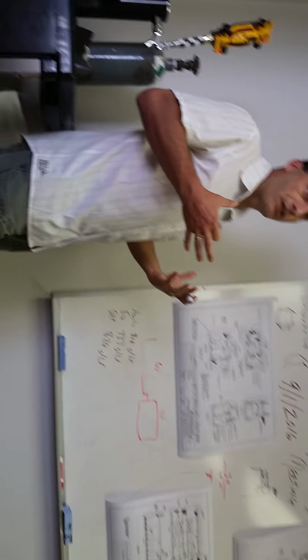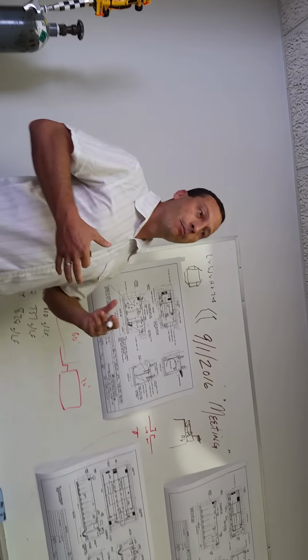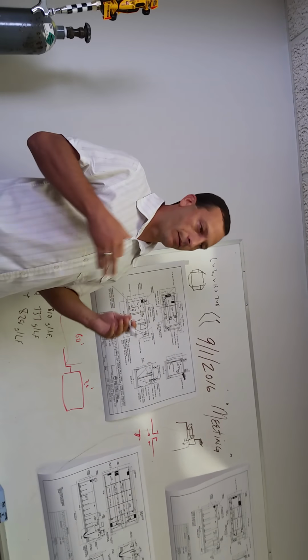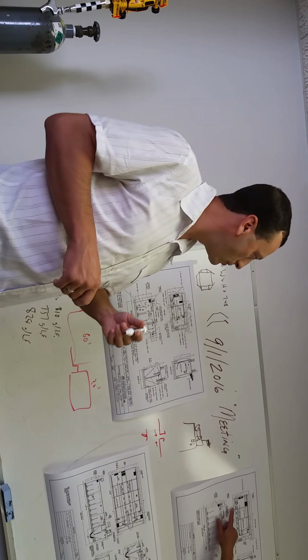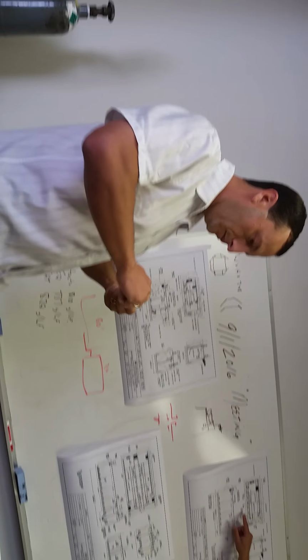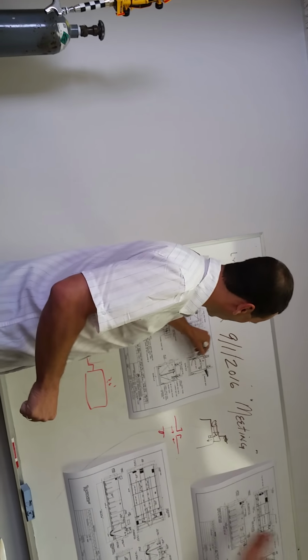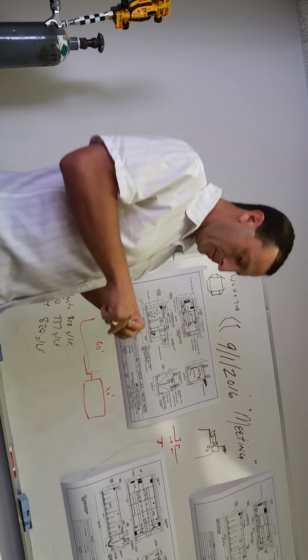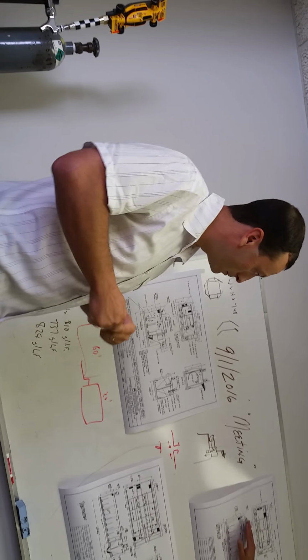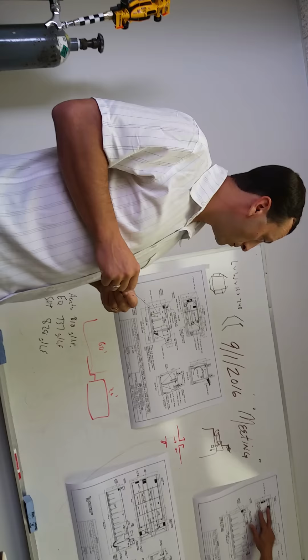So that's the other reason for the shape: we want those big tanks. They're inefficient at transferring oxygen, but they're really good at moving water around. As you can see in this drawing, we only have diffusers on one side of the tank. So the air comes up on this side, forces the water, and that creates roll. Otherwise, if you just had square walls, you're going to have to either put these in the center or have them on both sides.